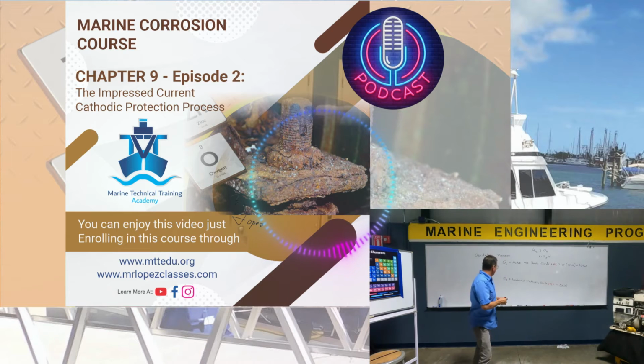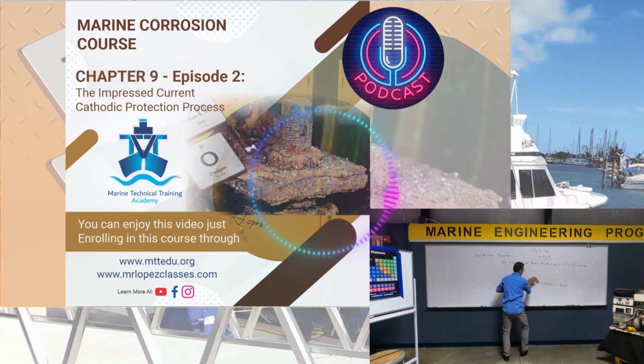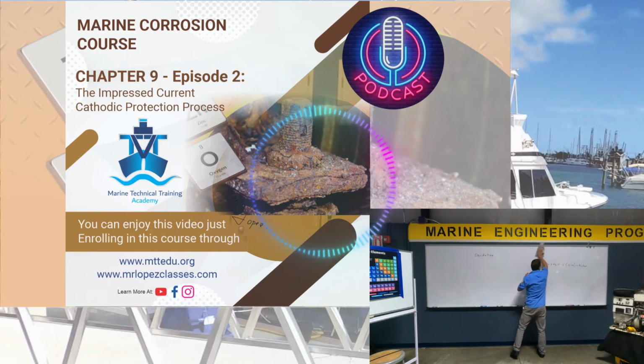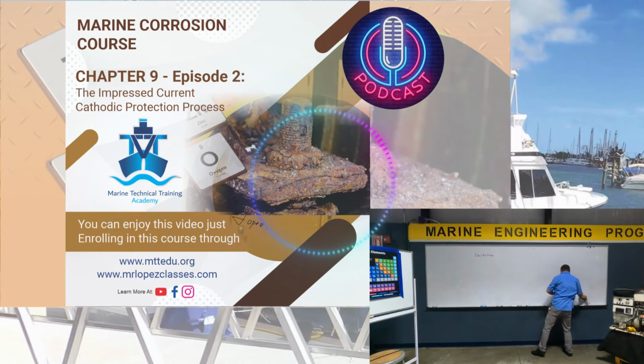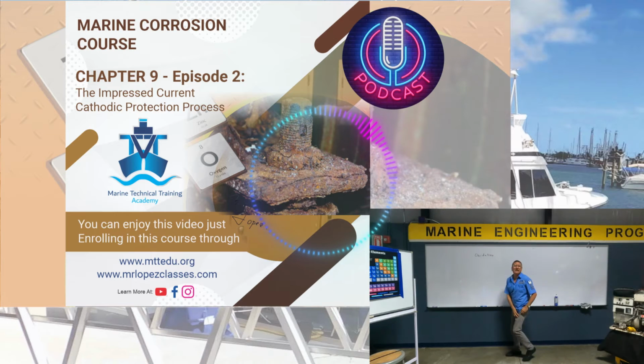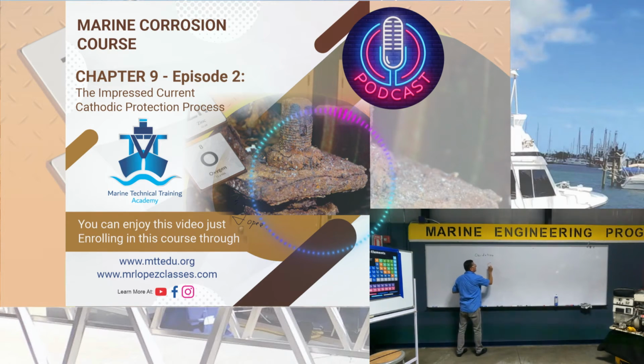Because the driving voltage is provided by the DC, the source of power, the anode is not necessarily more active. You don't need to check. It is not a sacrificial anode, because really in this system, this is not a sacrificial anode. It's an anode to allow the flow of current to the structure. This is the function of this.